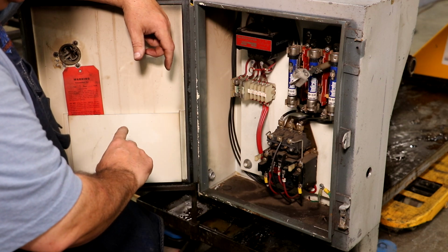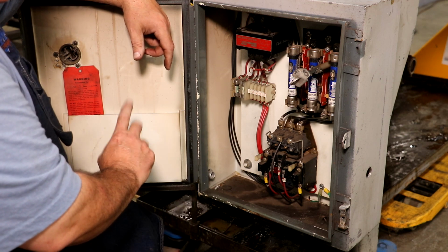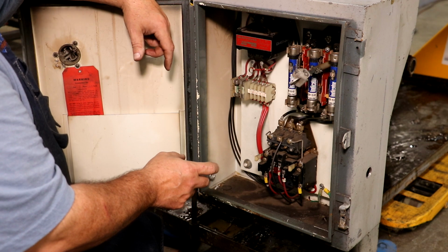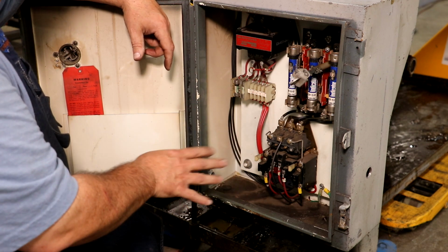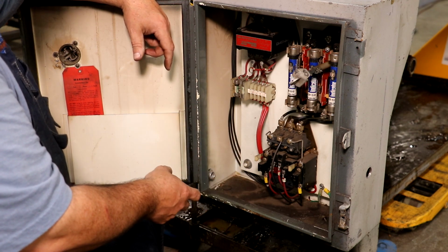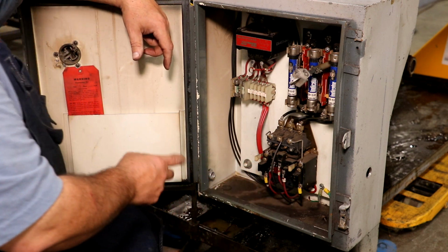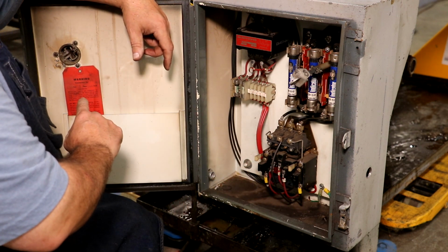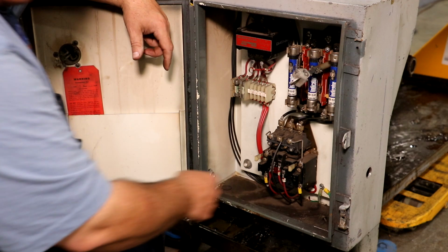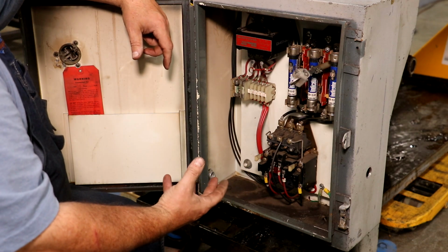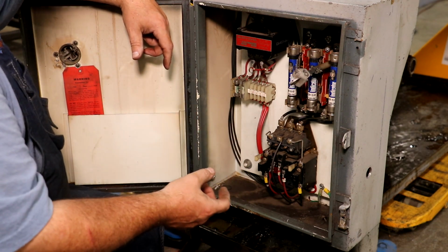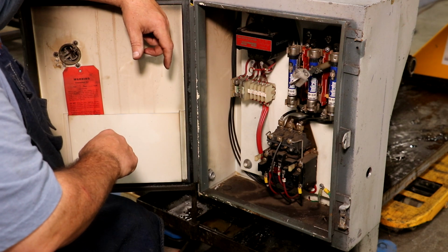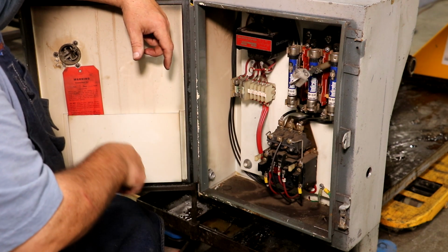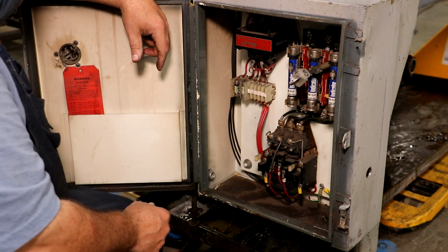Remember, I have a circuit breaker feeding this that's a 20 amp breaker. My motor, when I'm done, is going to be running at 5 amps. I don't want the breaker to trip at 20 amps - I want the switch to trip when I get to 5 amps, because if I'm drawing more than that, it's more than what the motor is designed for and you could damage it. That's something else that takes place in your motor starter.